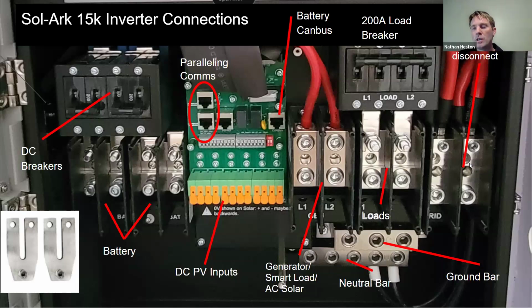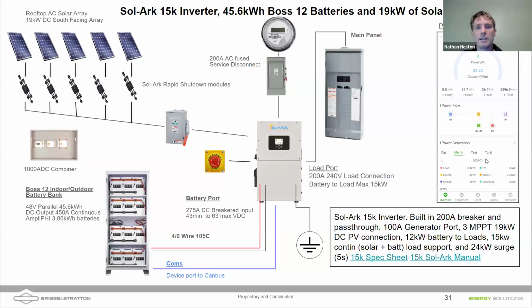Your grid connection here, again, I mentioned this is a 200 amp input. This has to be connected through a fused disconnect, and I'll show that in a second. So I'll point out again what the single line diagram looks like for connecting this. Again, that 200 amp service comes from your meter can. I've heard people say this is service entrance rated. I, in fact, have parroted that and was found out that I was wrong. Dylan from Sol-Ark let me know, no, you do have to put it through a fused disconnect. It's not service entrance rated. So come in through that, go into the grid port on that inverter.